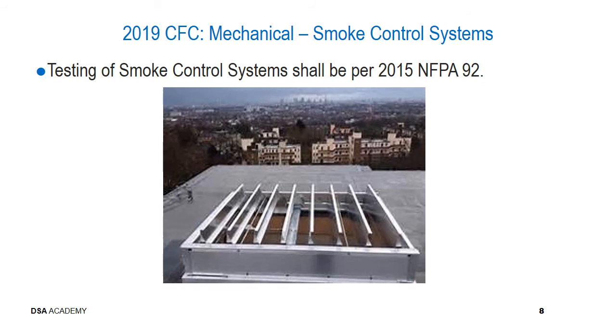Testing of smoke control systems shall be in accordance with the 2015 edition of NFPA 92. In addition to the regular inspection test requirements, smoke control systems shall undergo special inspection and tests sufficient to verify proper commissioning. Testing of smoke control systems shall be performed by a special inspector in accordance with CBC 1705.18. NFPA 92, Section 8.4.4.2 notes that if standby power has been provided for the operation of the smoke control system, the acceptance testing shall be conducted while on both normal and standby power.